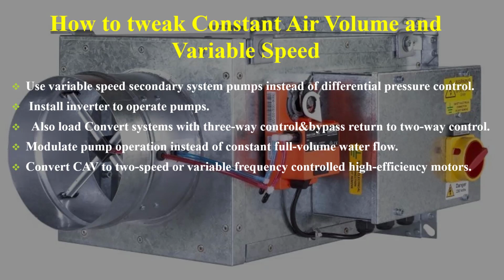How to tweak constant air volume and variable speed. Use variable speed secondary system pumps instead of differential pressure control. Install inverter or variable frequency drive to operate pumps. Also convert systems with 3-way control and bypass return to 2-way control. Modulate pump operation instead of constant full volume water flow. Convert constant air volume to 2-speed or variable frequency controlled high-efficiency motors.